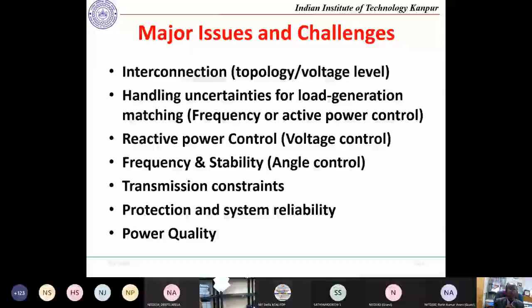Another concern is reactive power control and voltage control. As you know, voltage is a local phenomenon. It's not that generators alone control it through synchronous generator excitation control. Voltage control is where we set reactive power, using various shunt devices like capacitors, on-load tap changers (LTCs) in transformers, thyristors, and even SVCs to control it.